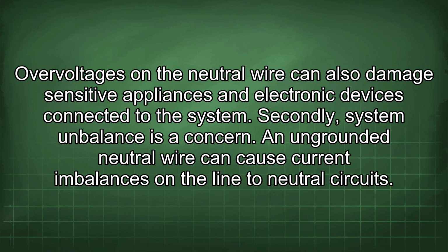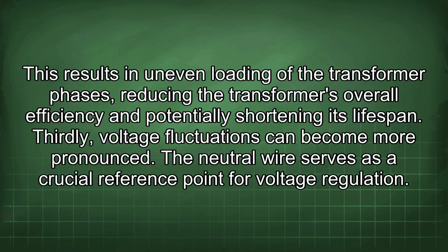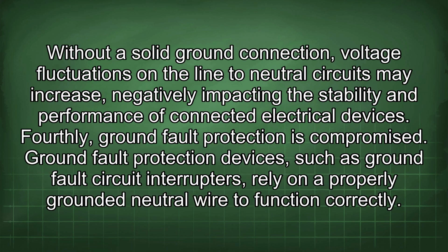Secondly, system unbalance is a concern. An ungrounded neutral wire can cause current imbalances on the line to neutral circuits. This results in uneven loading of the transformer phases, reducing the transformer's overall efficiency and potentially shortening its lifespan. Thirdly, voltage fluctuations can become more pronounced. The neutral wire serves as a crucial reference point for voltage regulation. Without a solid ground connection, voltage fluctuations on the line to neutral circuits may increase, negatively impacting the stability and performance of connected electrical devices.